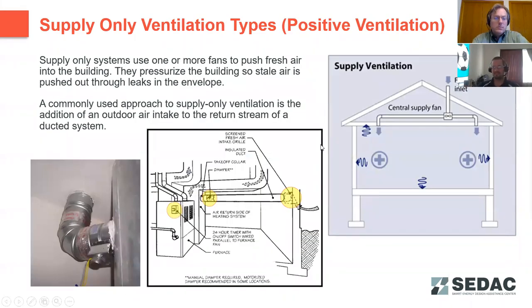Probably the next option that we see is supply only. This one actually seems to me to be more rare, probably because with this system, you've got to add a timer to your supply fan on your residential system so that it's bringing in outside air on a regular basis for ventilation purposes.